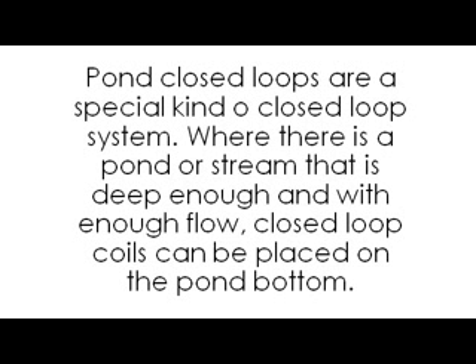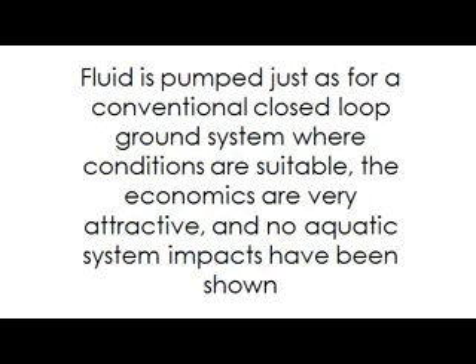Pond loops. Pond closed loops are a special kind of closed loop system. Where there is a pond or stream that is deep enough and with enough flow, closed loop coils can be placed on the pond bottom. Fluid is pumped just as for a conventional closed loop ground system where conditions are suitable. The economics are very attractive and no aquatic system impacts have been shown.